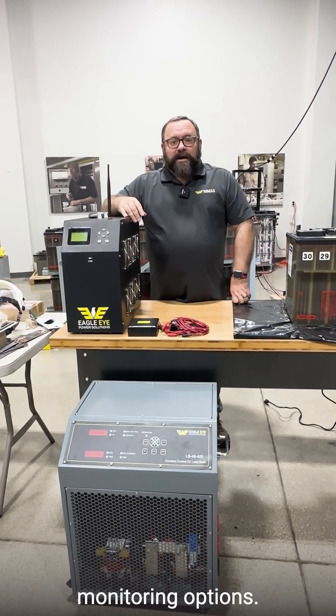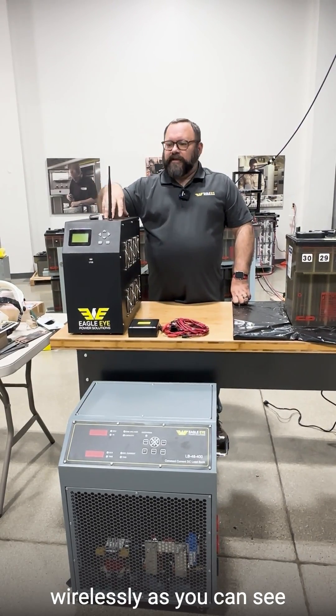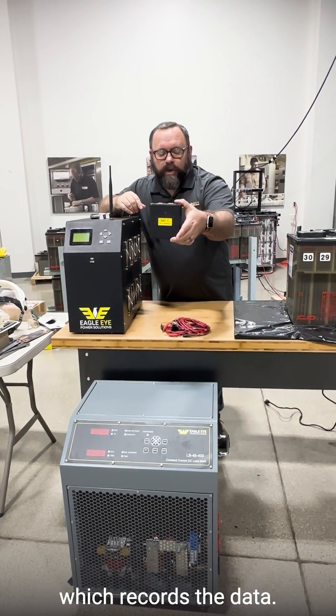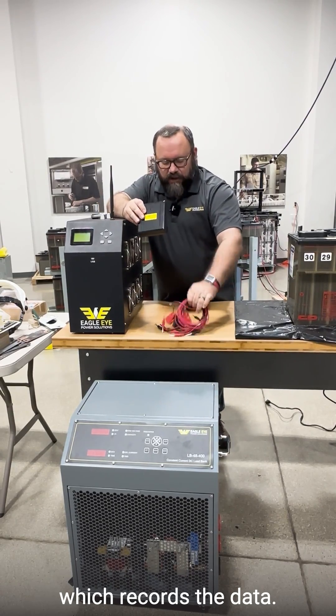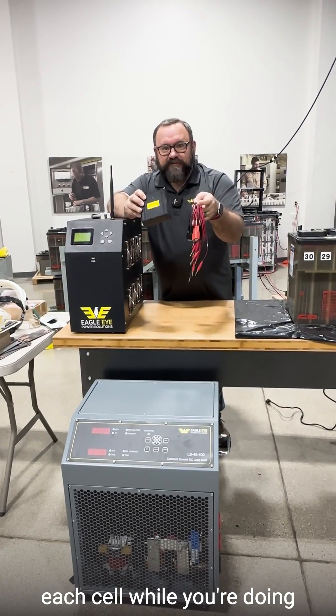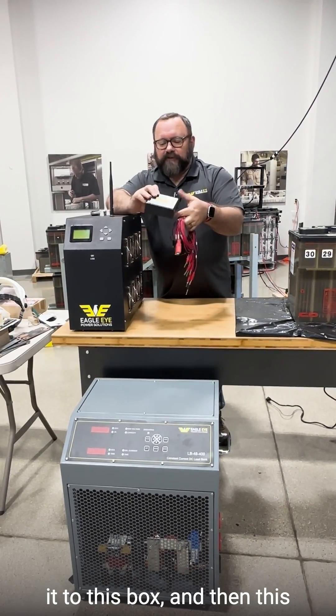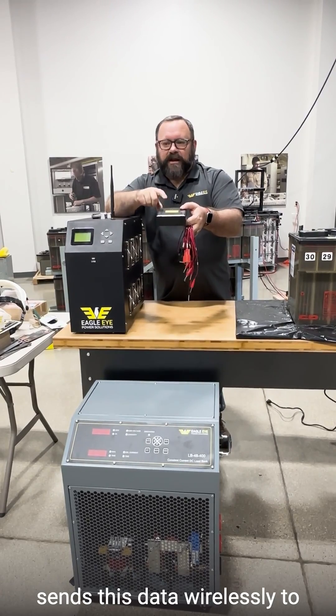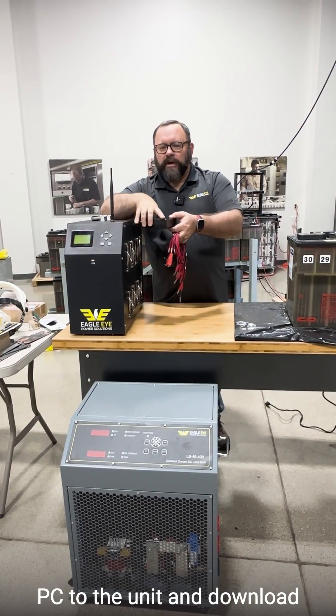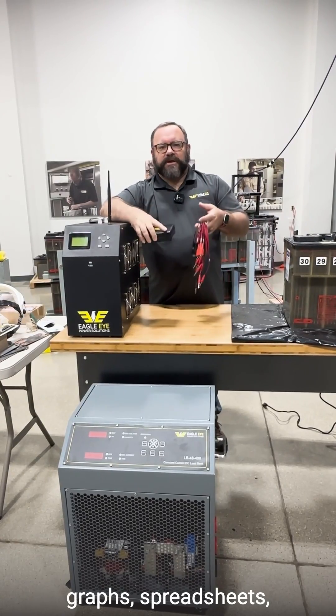They both have cell monitoring options. One difference is that the SLB unit does it wirelessly — you can see the little antenna here. It uses the DAQ system which records the data. You hook it up to the cells, it transmits the data of each cell while you're doing the discharge test, transmits it to this box, and then this sends the data wirelessly to the antenna. You can then connect your laptop or PC to the unit and download all the data into charts, graphs, spreadsheets — whatever you need.